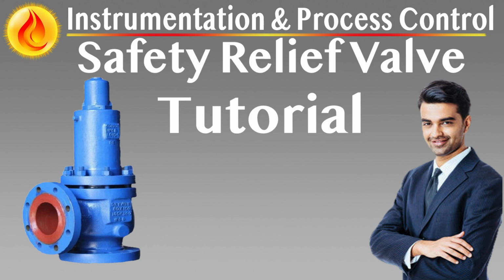Key applications and suitability. Pilot-operated valves are preferred when tight operating margins exist between maximum operating pressure, MOP, and relief valve set pressure, typically 10%. High back pressure conditions are expected, typically 50 to 70% of set pressure. Superior sealing is required to minimize leakage and fugitive emissions. Large flow capacity is needed without the bulk of a large spring-loaded valve. Longer stroke and high lift requirements exceed the capabilities of spring-loaded valves.